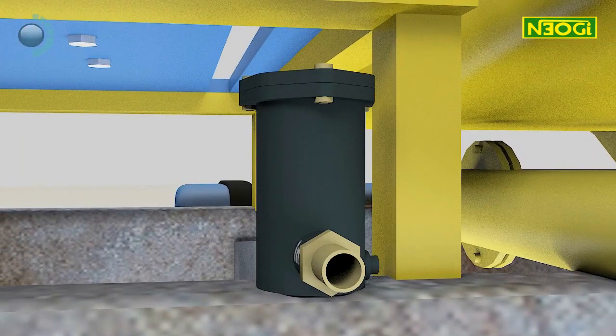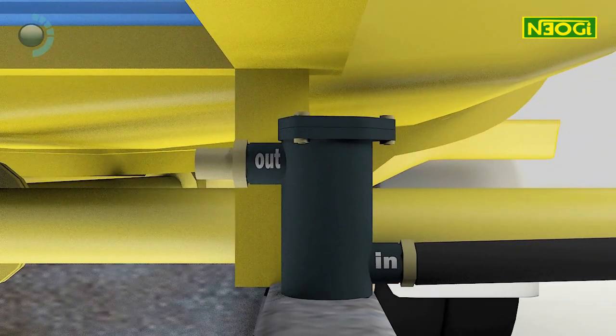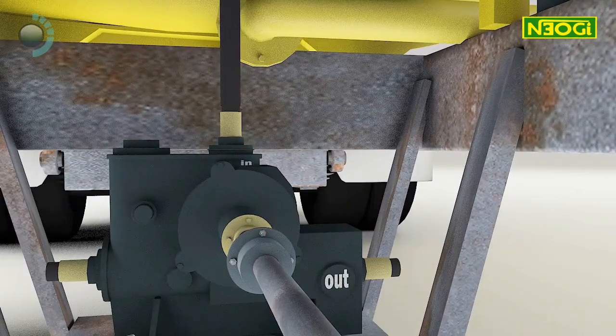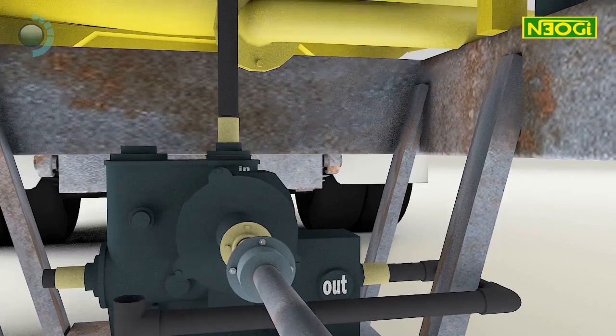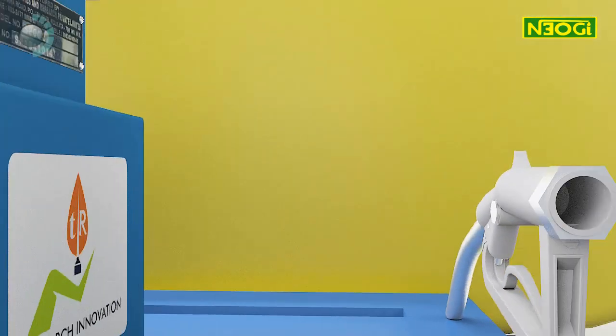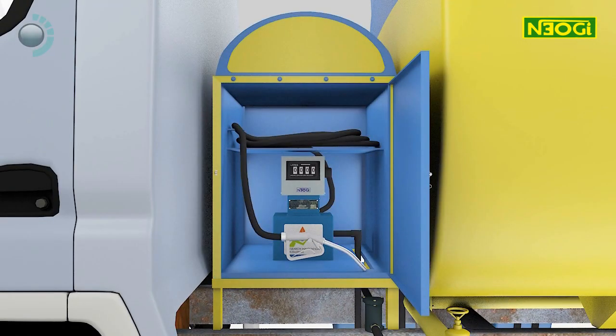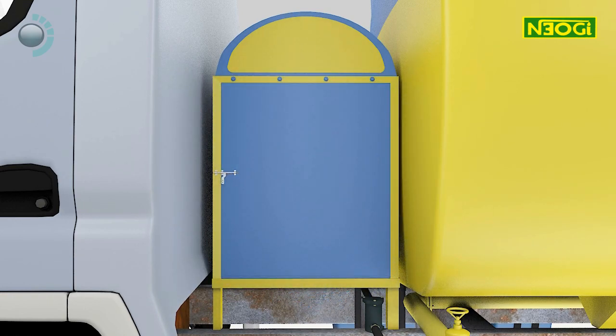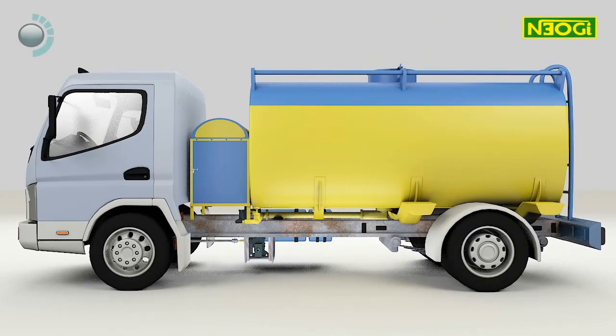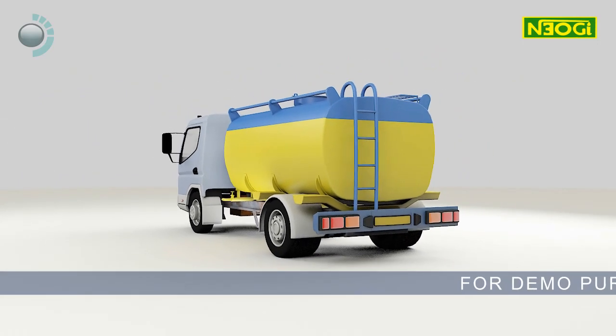The filter is installed such that the pipe from the stop valve of the tanker is connected to the input of the filter. The output of the filter is connected to the input of the pump. The output of the pump is connected to the input of the flow meter. The output of the flow meter is connected to the nozzle via hose pipes. It is good practice to make a covered box to fit all these components, to protect them from rain or physical damage, while ensuring the box is easily accessible from all directions for proper maintenance.